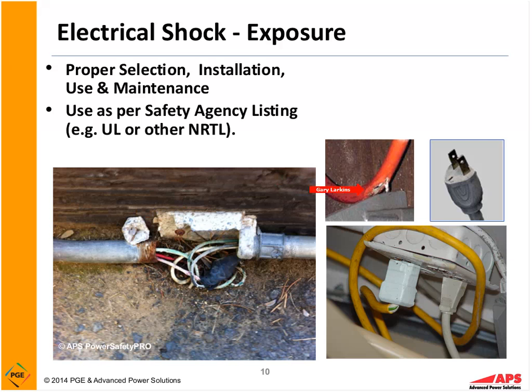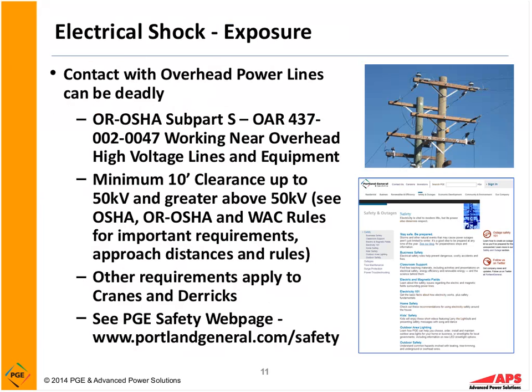Okay, right there we could see the cord is damaged. Someone picks that up or it's sitting in water, we could have electrical current flow. Just below it here, we have another damaged cord where the insulation is pulling out. And in the upper right-hand corner here, we can see that we're missing a ground pin on our cord. So in essence, we've lost our safety ground, which can definitely cause problems when we look at the use of portable cords and tools. Many people have been electrocuted because the safety ground is missing. It's absolutely essential we inspect our cords and tools and use them properly.